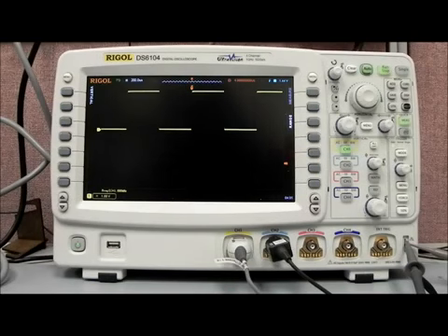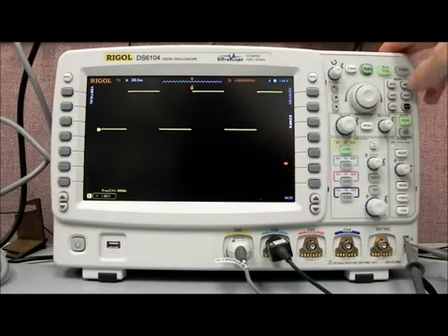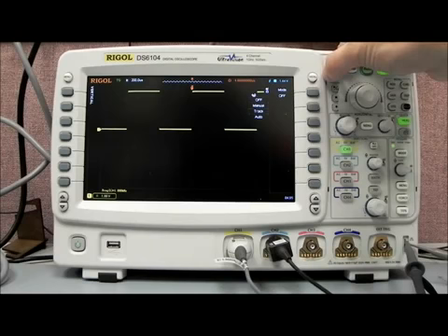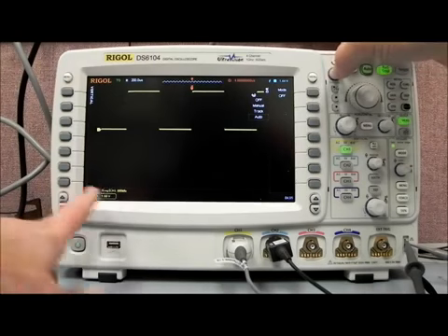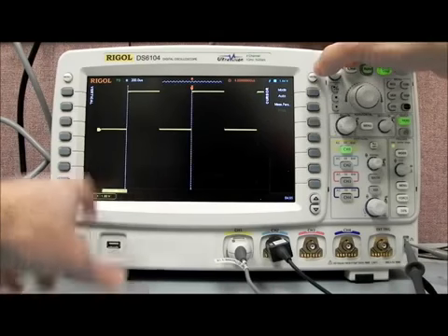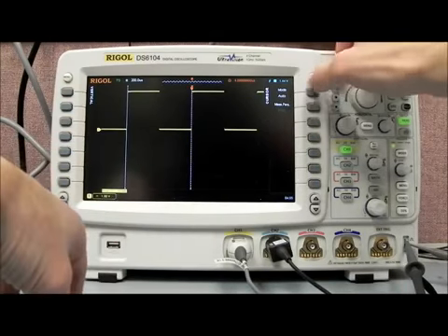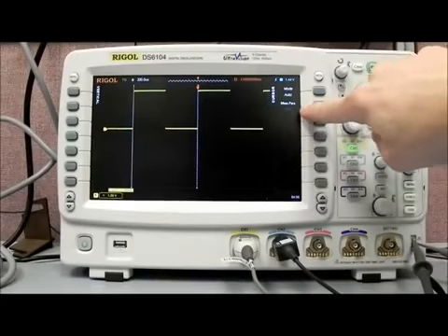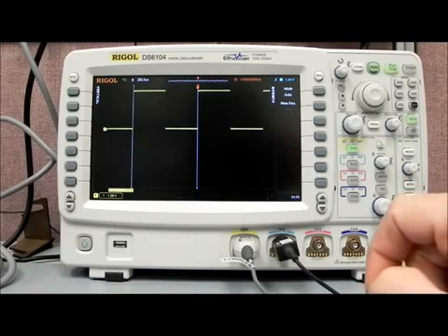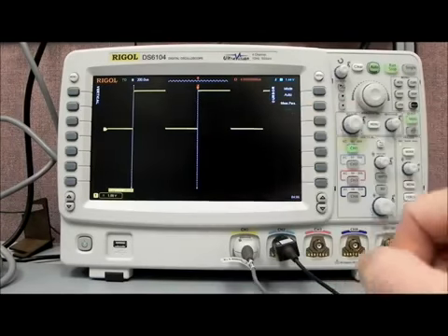And we can also do some other things with measurements and cursors. If we come over here to the cursor area in the menu, pull cursors, and we have a few different modes. We have manual, tracking, and auto. If we have a measurement pulled up over here, and we hit auto, it will actually give us the measurement parameters frequency. See how it says measurement parameters frequency? And now it's indicating where it's making those frequency measurements. And it's been highlighted, which is really nice.